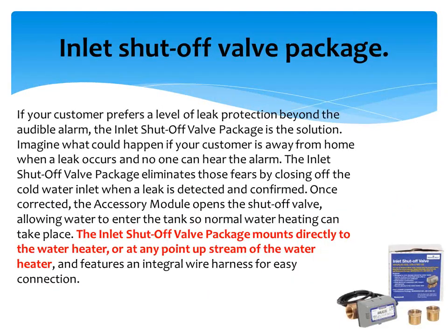So it's mounted in the drain pan or whatever. It could be a condensation problem, it could be a relief valve blowing off and getting into the pan, not something that normally would go on. You can reset it and the alarm shuts off. If you have a real life situation where once again, condos and apartment buildings and stuff like that, where you're concerned about damage to other floors, we actually have a shutoff valve set up for them that operates off that same module. So now we can sense the water on the floor or in the pan, and we can actually shut down the incoming water of the water heater.